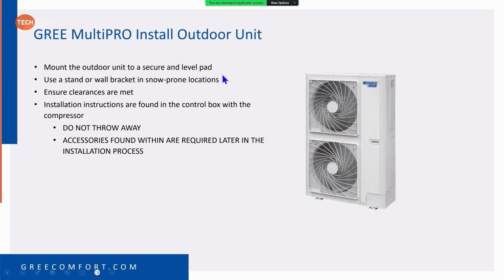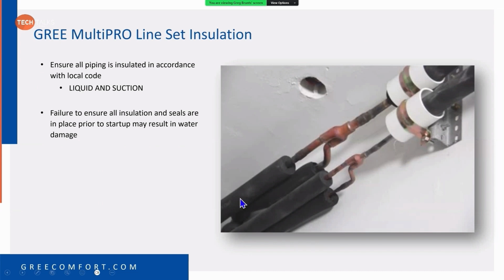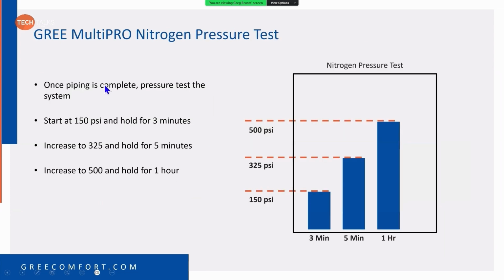So obviously you mount your outdoor units, make sure it's secure, and use a stand or wall bracket in snow-prone locations. This is very much like we were talking about with the flex unit. You don't want this thing right on a concrete pad. Remember, both pipes have to be insulated, liquid and suction. We do give you a nitrogen pressure test recommendation. Start with 150 PSI for 3 minutes, increase it to 325 for 5 minutes, 500 pounds for 1 hour, just to ensure you don't have any leaks, because the last thing you want to do is let that charge out of that condenser and then find out you've got a leak.